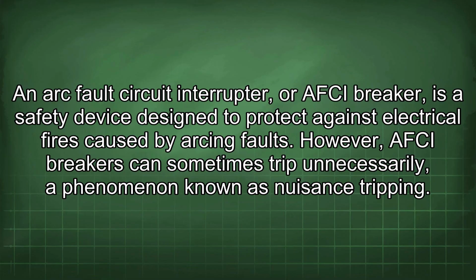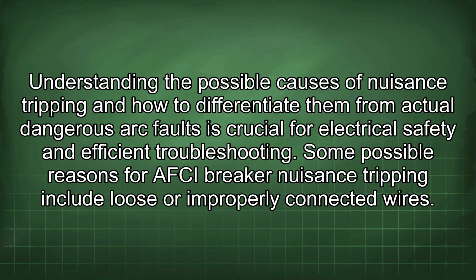An arc fault circuit interrupter, or AFCI breaker, is a safety device designed to protect against electrical fires caused by arcing faults. However, AFCI breakers can sometimes trip unnecessarily, a phenomenon known as nuisance tripping. Understanding the possible causes of nuisance tripping and how to differentiate them from actual dangerous arc faults is crucial for electrical safety and efficient troubleshooting.